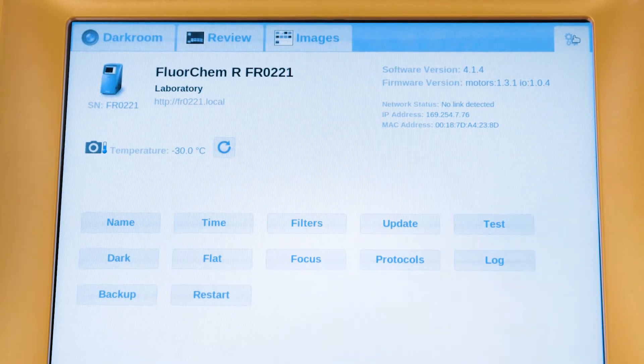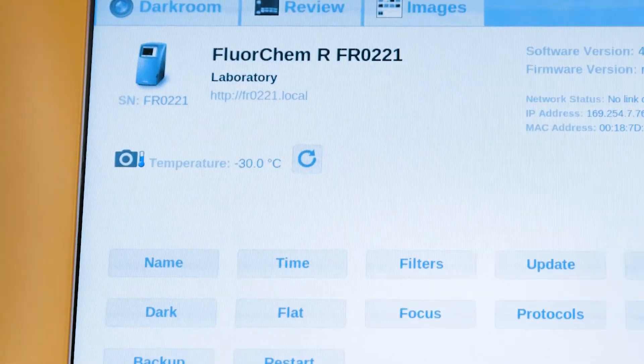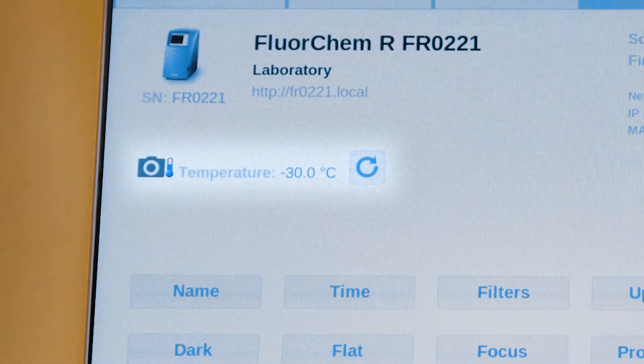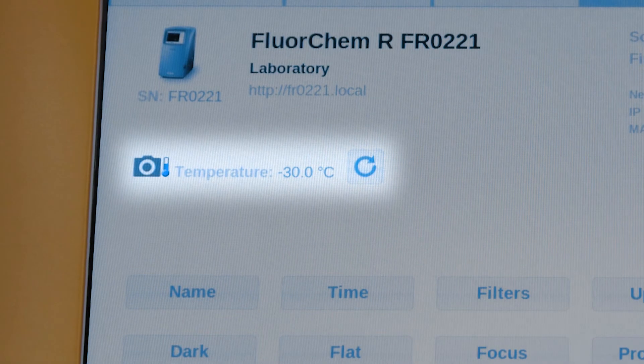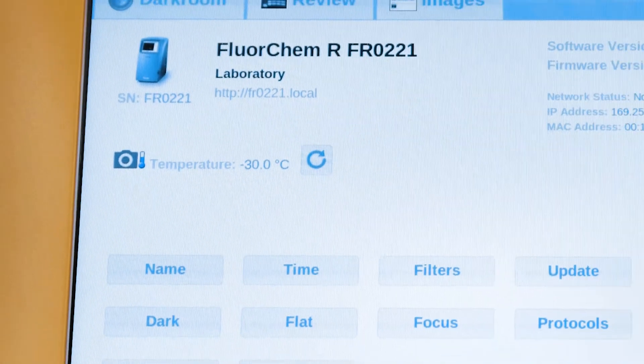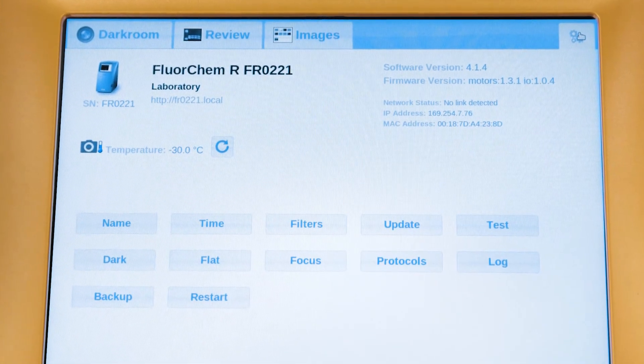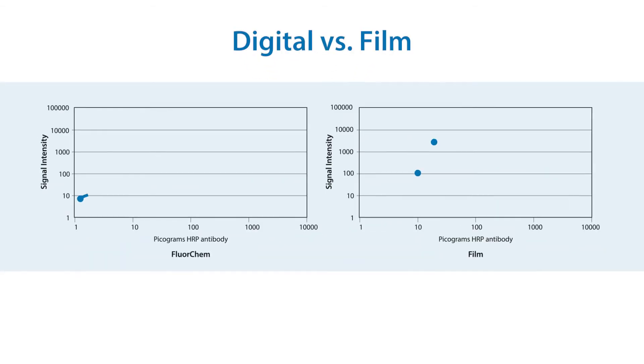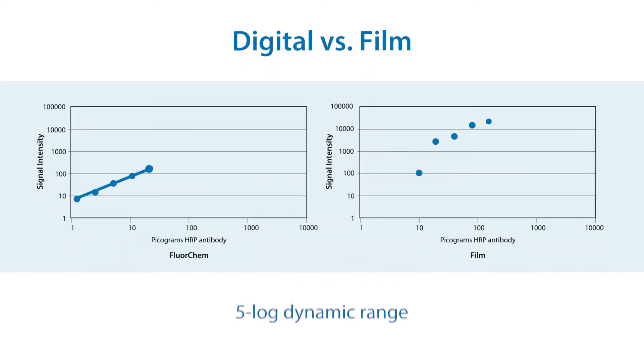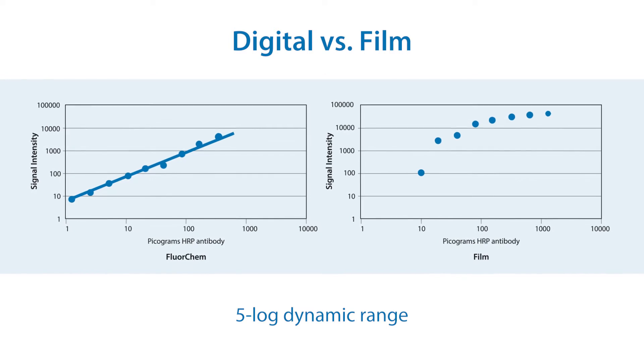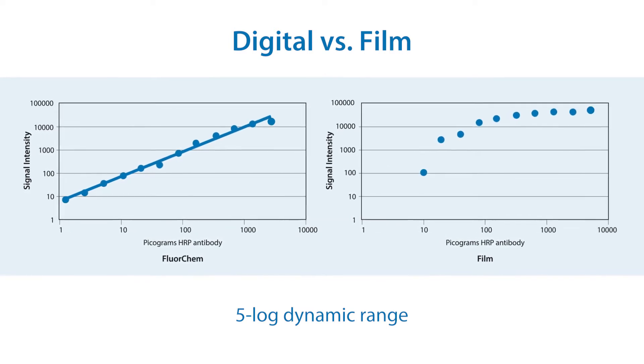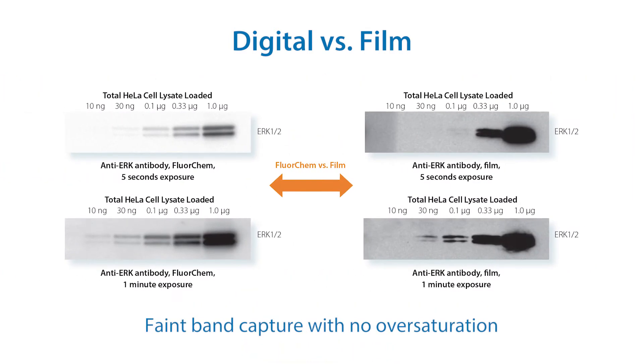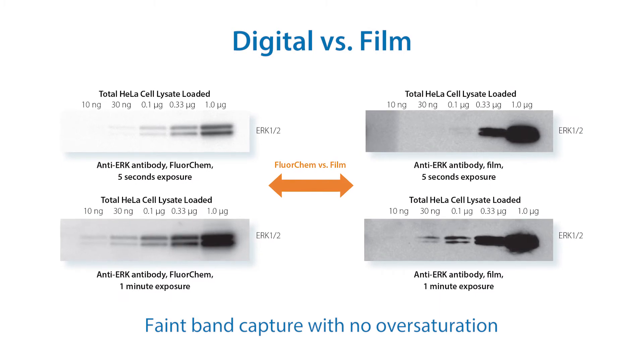The camera temperature is absolute and regulated, meaning that the system maintains the specified cooling temperature, so that you don't have temperature fluctuations if ambient temperature changes slightly. The CCD camera in the FluorChem Imagers have about a 5-log dynamic range, significantly better than film, allowing you to capture faint bands without oversaturating brighter signals, eliminating the need for multiple exposures.